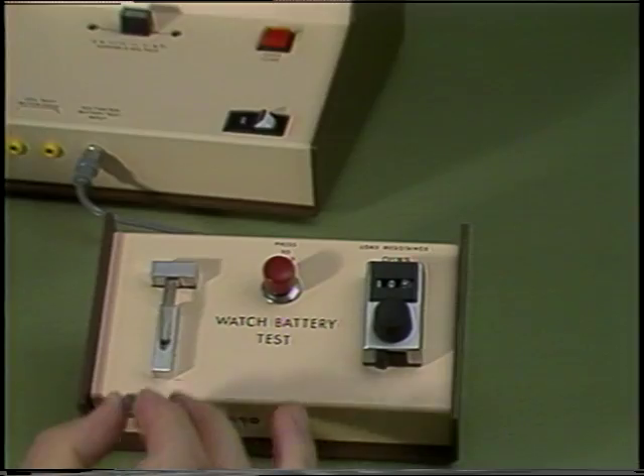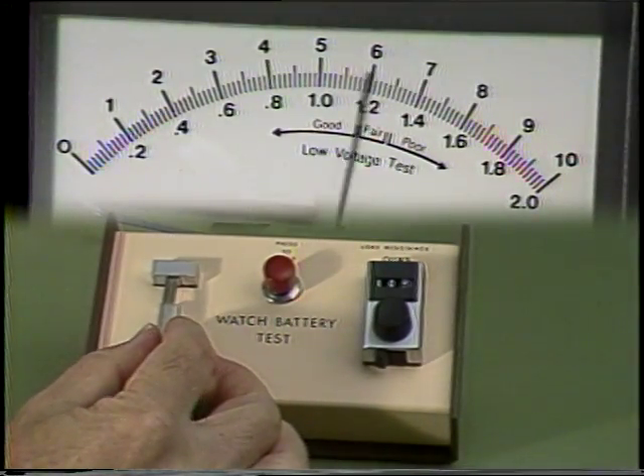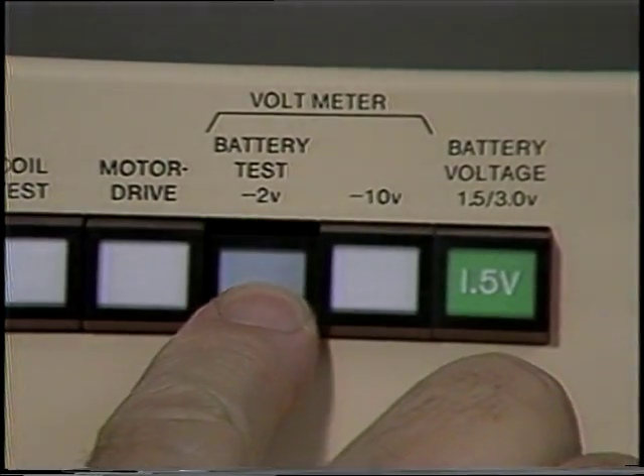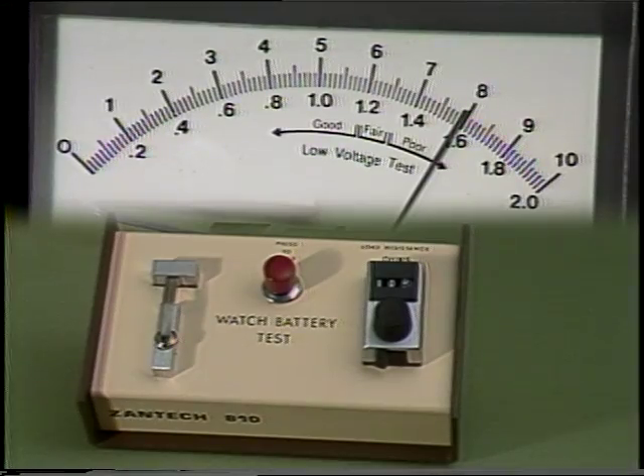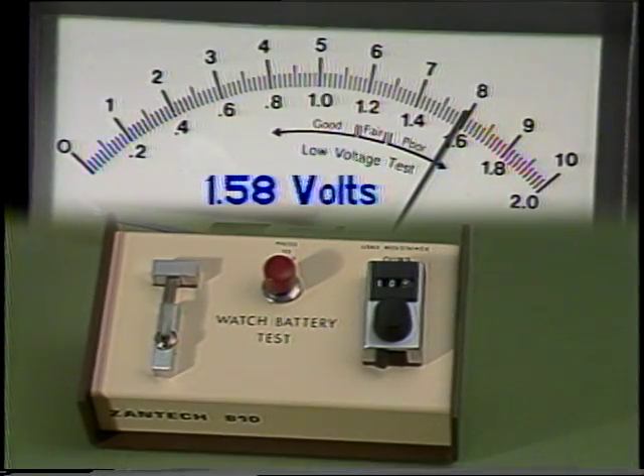To test a battery, slide it under the clip. Push in the 2-volt meter scale button and read the open circuit battery voltage on the 2-volt range of the meter. New silver oxide batteries measure 1.58 volts.